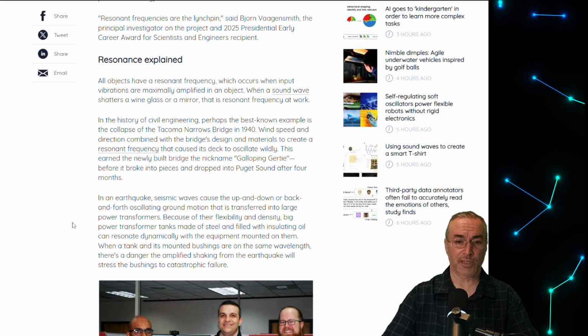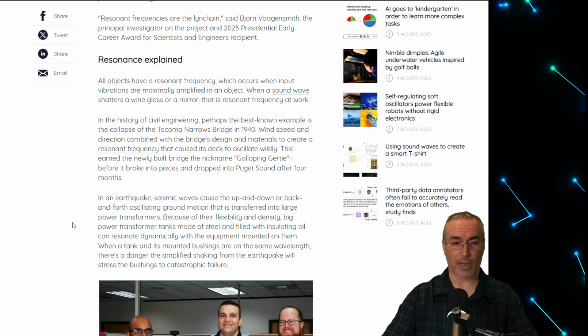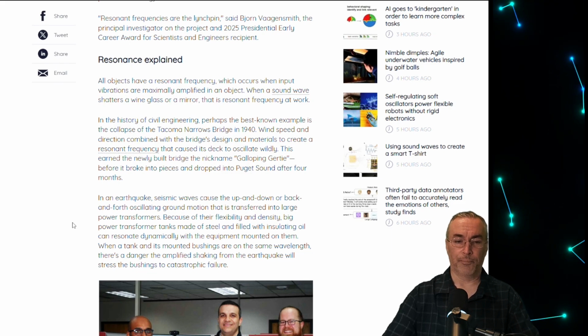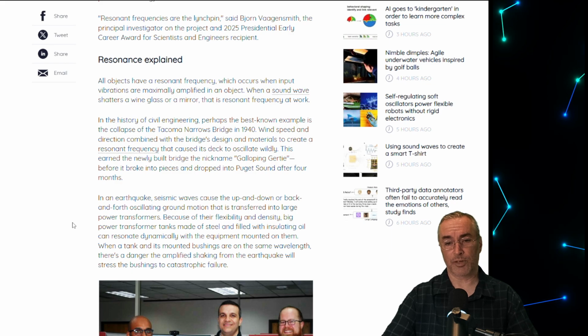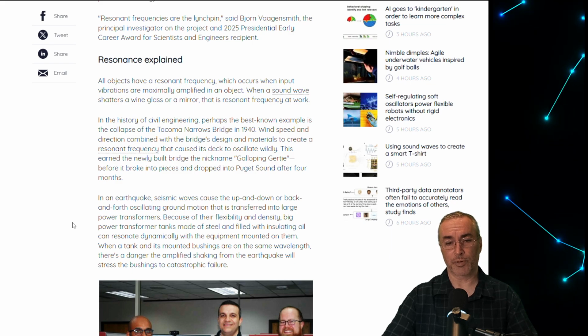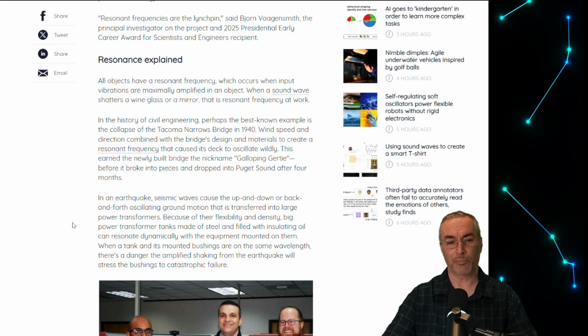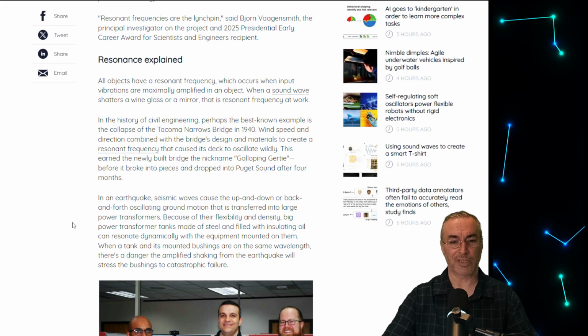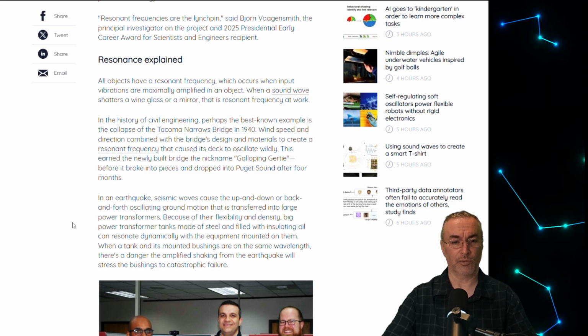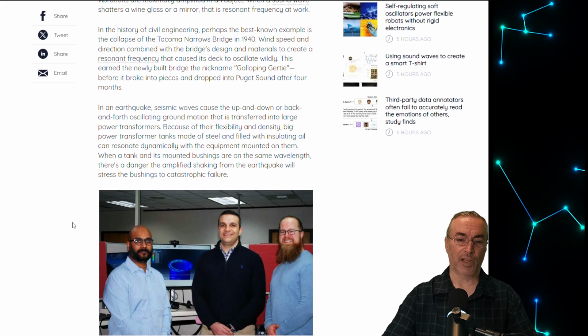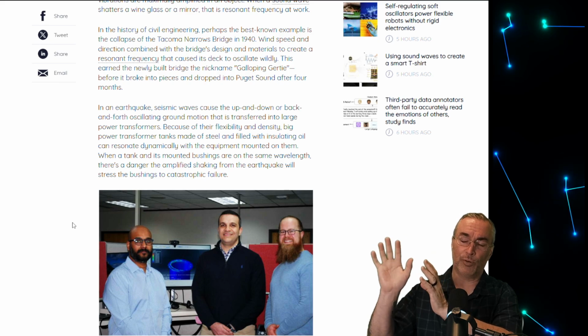So in an earthquake, seismic waves cause up and down, or back and forth, or both motions on the ground, and that is transferred into the large transformers. Because of their flexibility and density, big power transformer tanks made of steel and filled with insulating oil can resonate dynamically. You actually see these transformers up on poles.